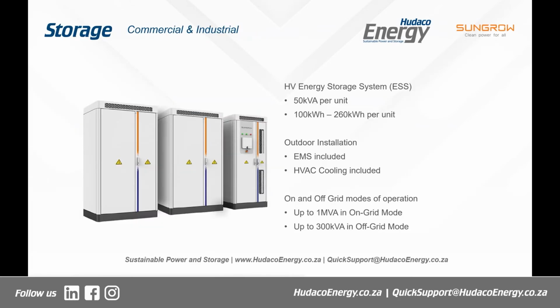Yeah, next one. And let's move right on to the hero of the day. This is the new commercial and industrial storage solution coming. It's made up of 2 or 3 parts. On the right-hand side of the image, you can see the PCS, the power conversion system. Inside there, you've got a 50 kVA hybrid inverter. You've got a 50 kVA transformer. You've got your EMS, your energy management system. You've got your HVAC control. You've got your protection for your AC circuits. And you've got HVAC and fire safety system.